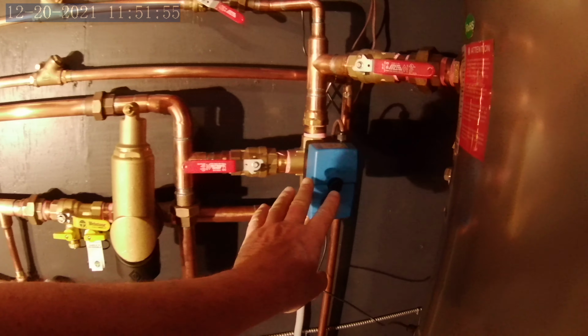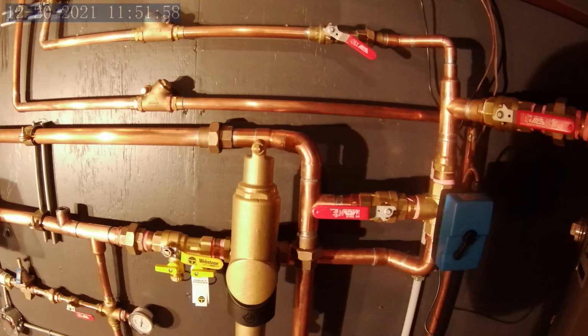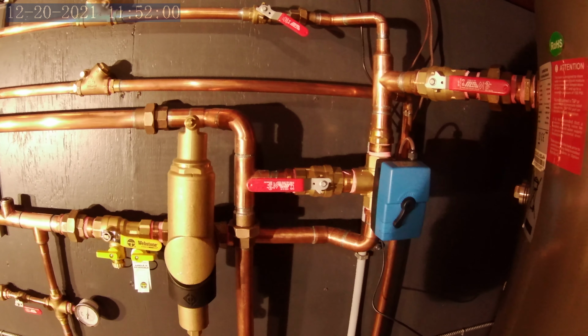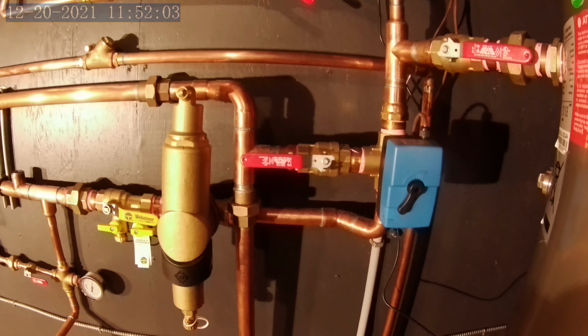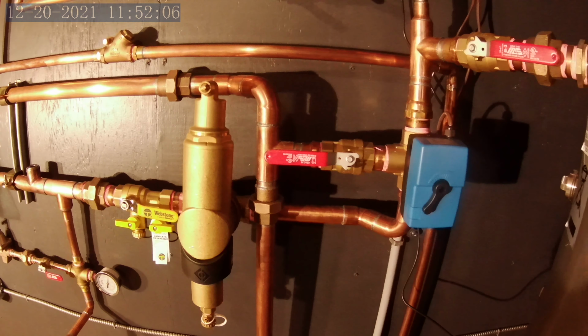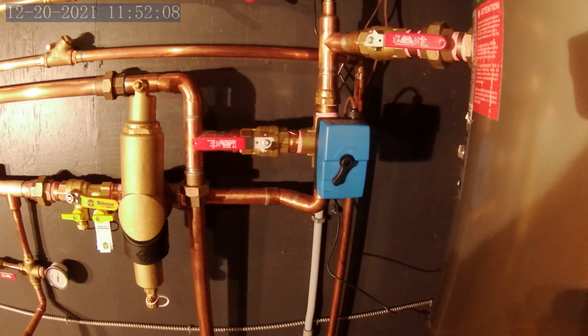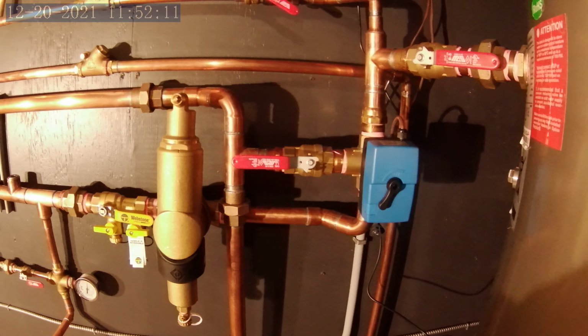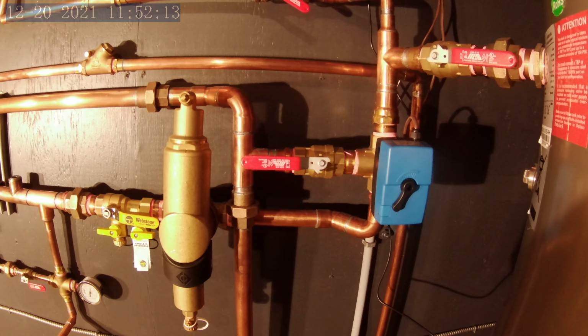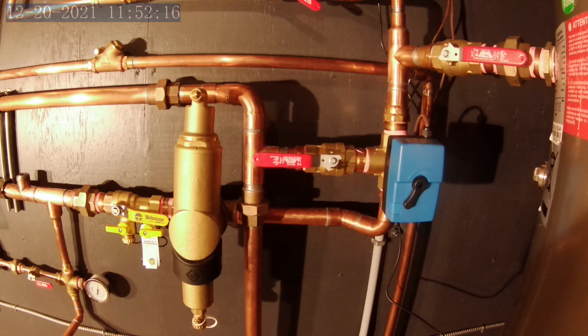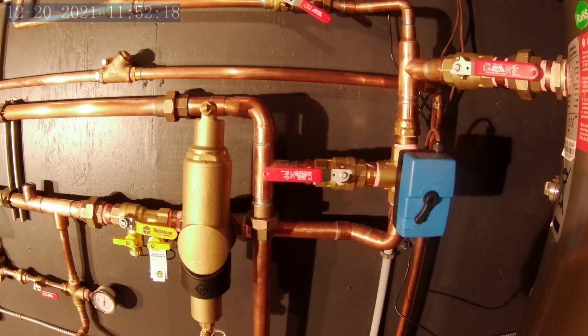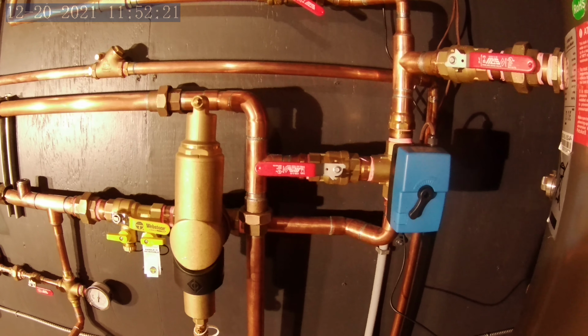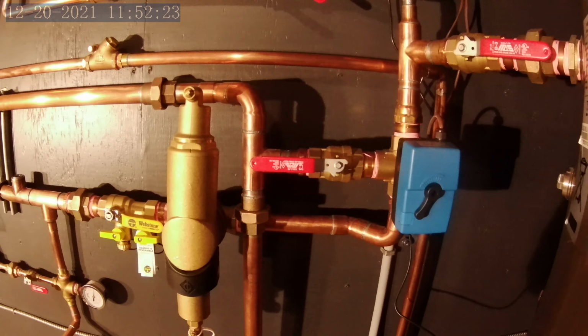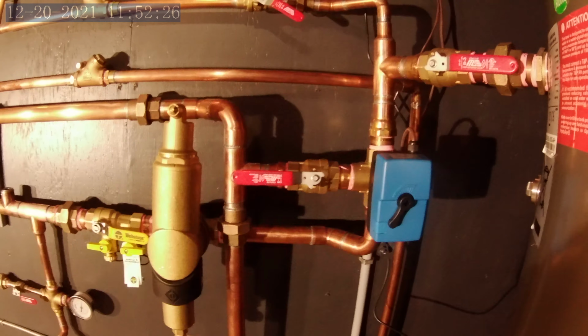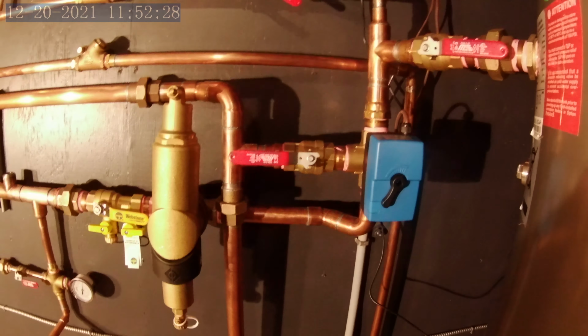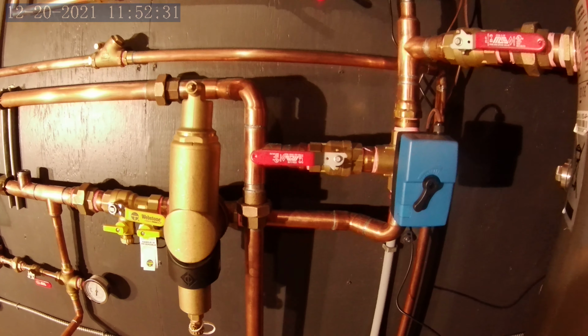So the master brains are going to use the outdoor temperatures and figure out the optimal temperature to store the water in the buffer tank. This is in the heating system. And then we're going to be storing the water in the buffer tank higher than what's needed in the panels, just so that the heat pump doesn't have to cycle as often. And then the mixing valve is what takes it down to the temperature needed by the panels themselves.